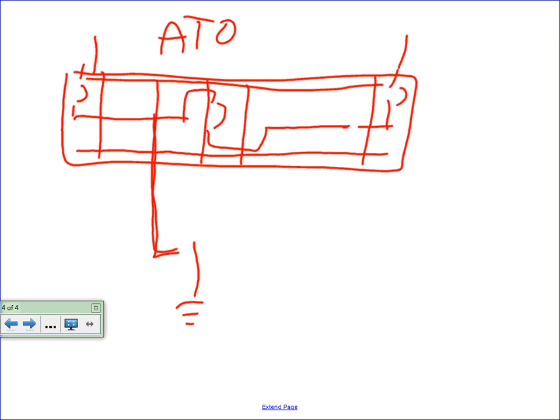So we can either use integral ground fault protection on that main or a separate relay, but either way, they kind of work the same. You set up the current and the delay, and you say, okay, 800 amps at 0.3 seconds. So if it's seeing it's missing 800 amps, it'll wait 0.3 of a second, but it'll blow that main.